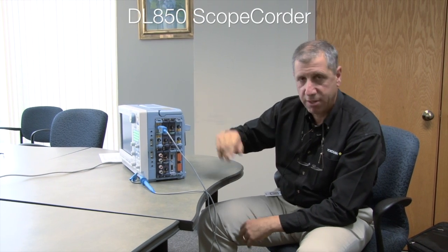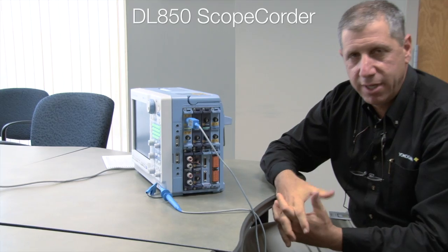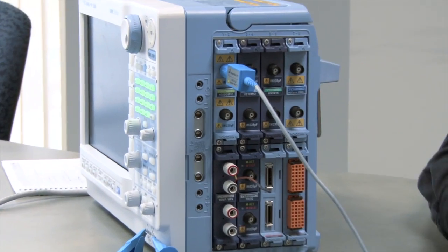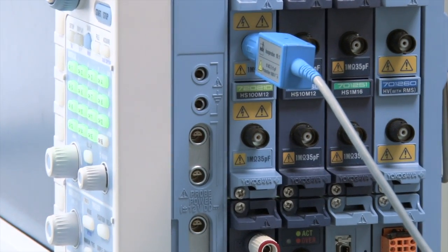We use up to 15 different test modules on the side. Most of these are all optically isolated, so if any high power overvoltage comes in, the mainframe is protected.